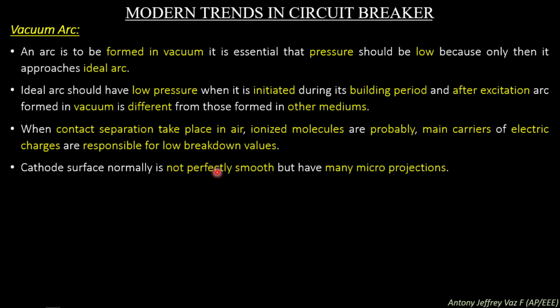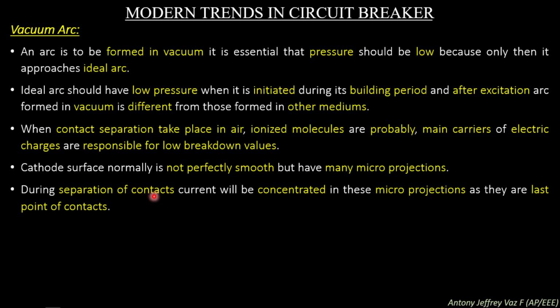The cathode surface is normally not smooth but has many microscopic projections. So in a vacuum circuit breaker, the moving contact and the fixed contact are present in a perfect vacuum. When the contact is examined, the cathode surface of the contact is not perfectly smooth. It will have many microscopic projections. During separation of contacts, current will be concentrated in these microprojections as they are the last points of contact. So at these microprojections a large amount of charge will be concentrated.